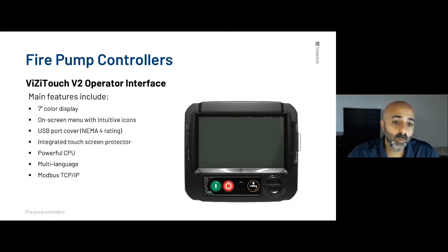Let's talk about our V2 operator interface — the most important icon inside the Tornatech fire pump controller. It comes with a seven-inch color graphic display with on-screen menus and intuitive icons. It has a USB port cover which gives it a NEMA 4 rating, so the display itself is watertight even though the closure is NEMA 2 standard. It has an integrated touchscreen protector. Due to its powerful CPU, you have the option of selecting multiple languages directly on the display, and we also provide Modbus TCP/IP.